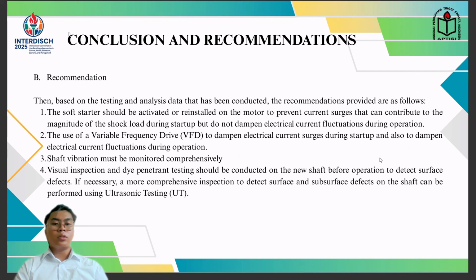One, the soft starter should be activated or reinstalled on the motor to prevent current surge that can contribute to the magnitude of the shock load during startup, but it does not dampen electrical current fluctuation during operation. Two, use a variable frequency drive to dampen electrical current surge during startup and also to dampen electrical current fluctuation during operation. Three, shaft vibration must be monitored comprehensively. Visual inspection and penetrant testing should be conducted on the new shaft before operation to detect surface defects. A more comprehensive inspection to detect surface and subsurface defects on the shaft can be performed using ultrasonic testing.